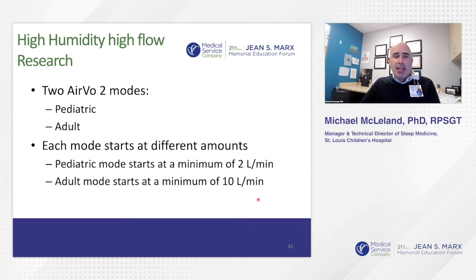So if you use a pediatric cannula, the machine is sensitive enough to know that it won't let you put the machine into an adult mode. If it is an adult mode, when you turn it on and you have a pediatric cannula hooked up, it will throw an error and it will kind of shut down. It won't let you continue on. And vice versa with the adult cannula, you can't run it in a pediatric mode. The machine is sensitive to know, and it can sense the flow coming in and out of that cannula, and it'll throw an error where you can't use it.